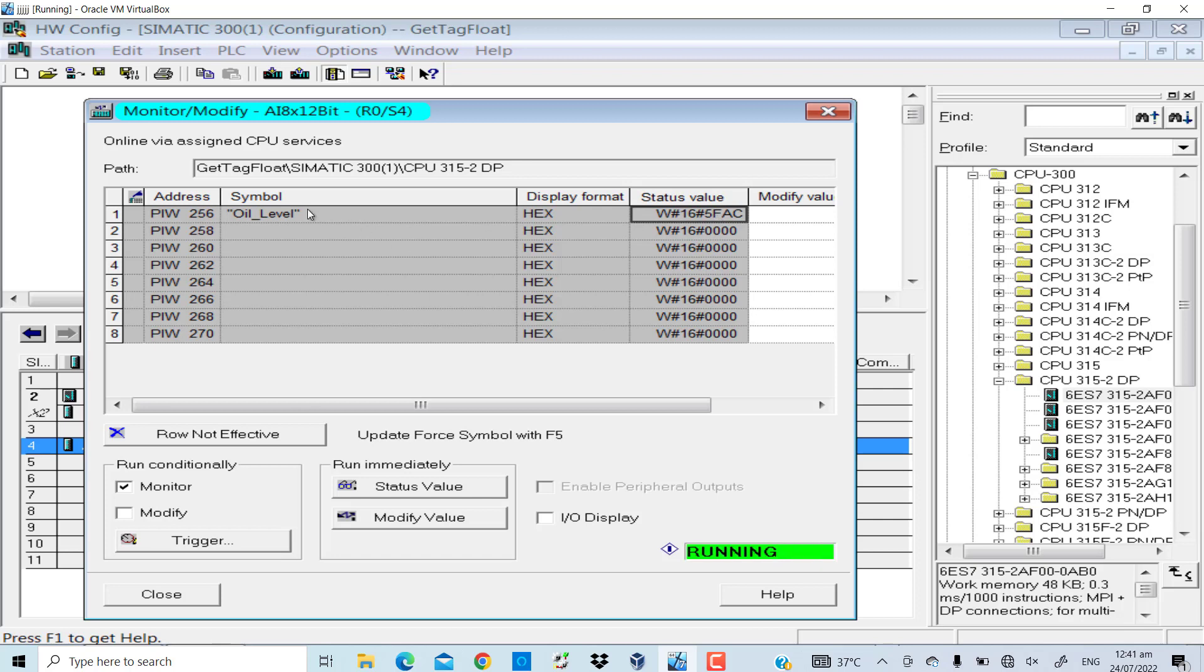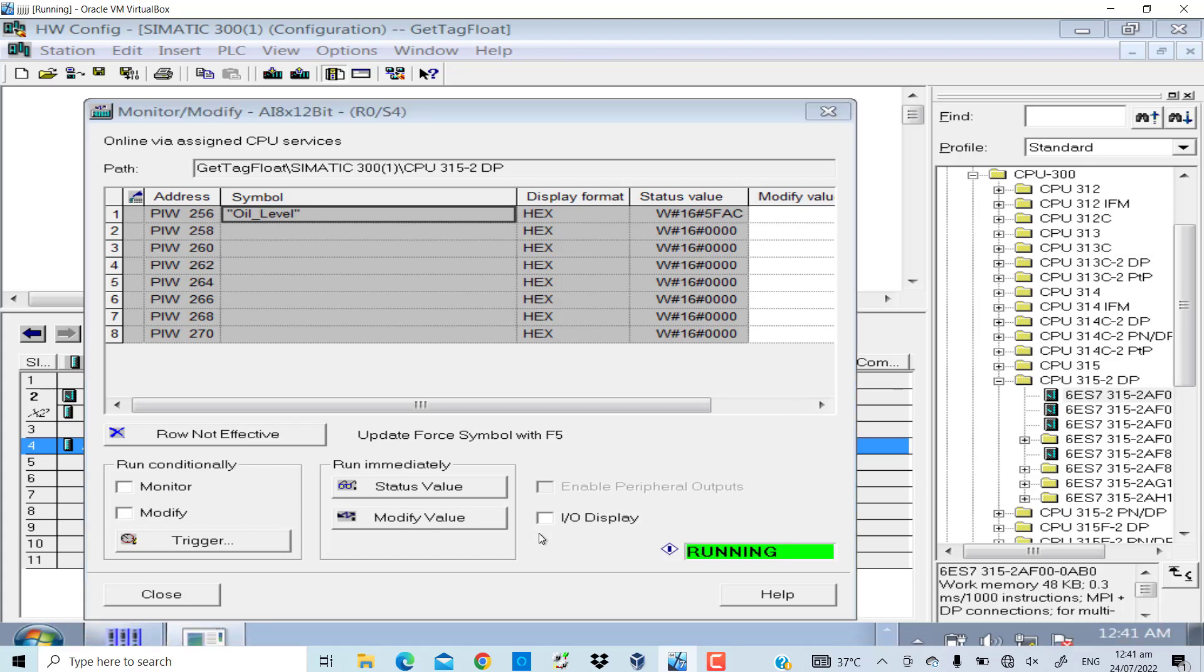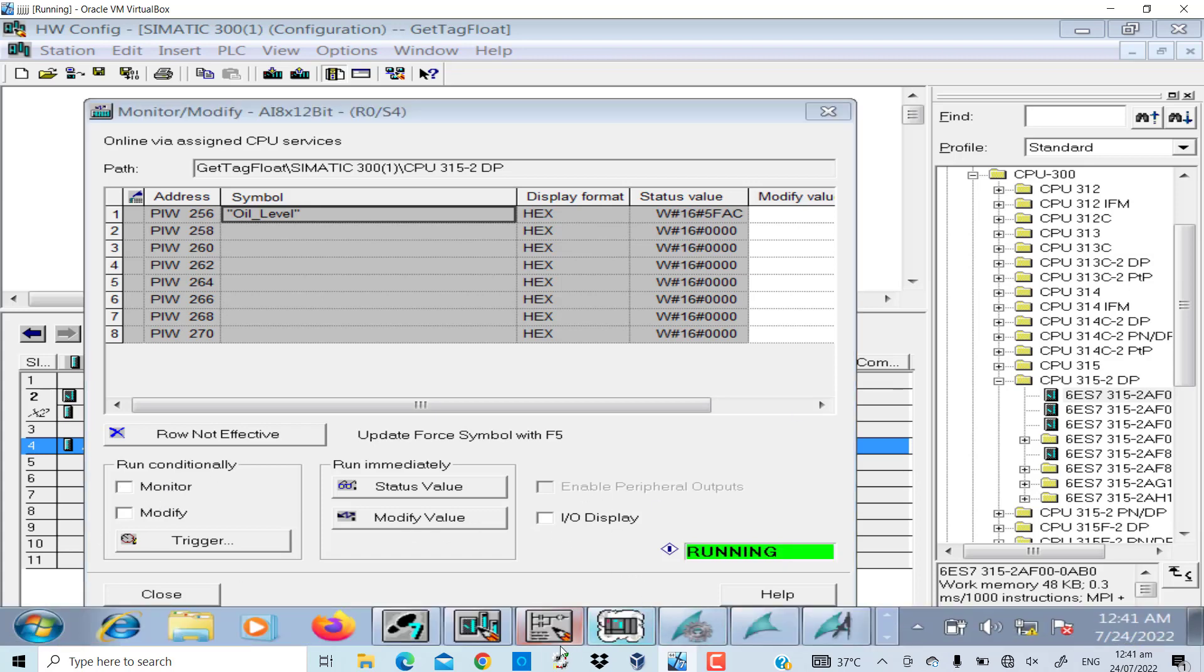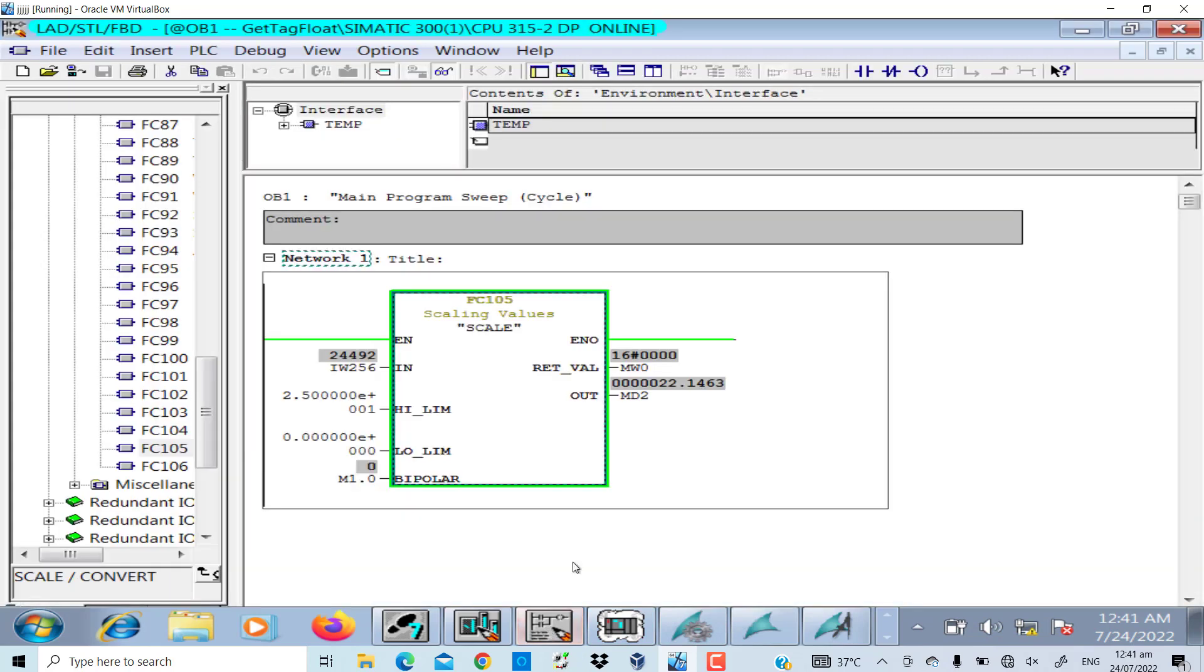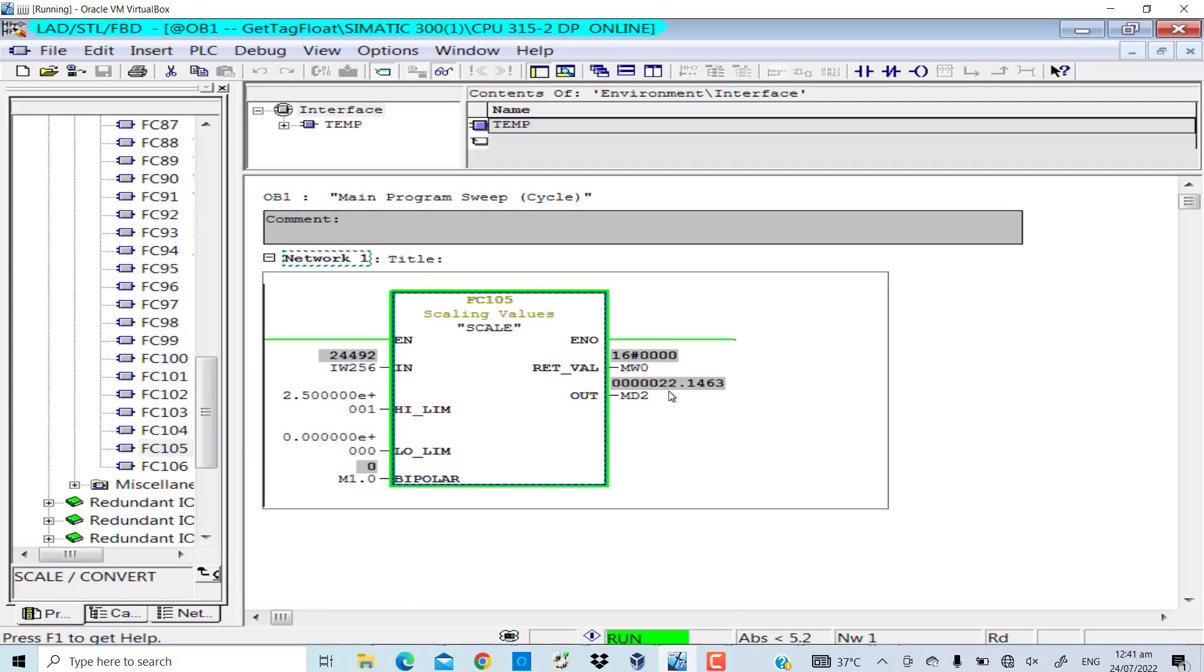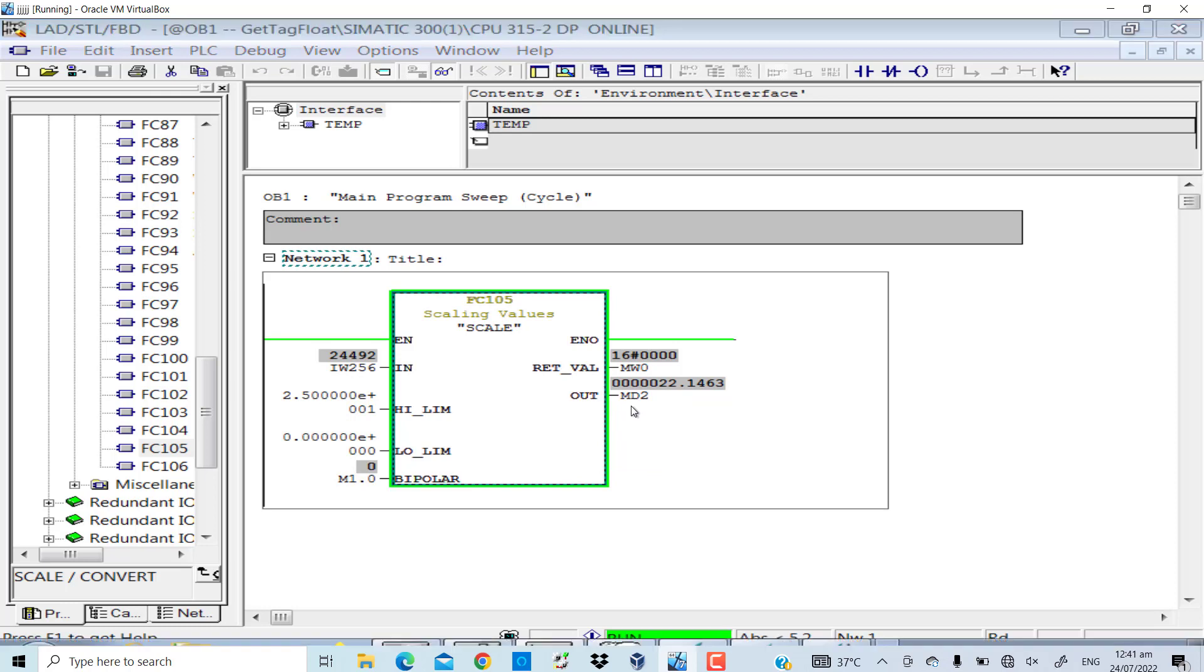The oil level is scaled according to the logic. The value 22.14 is the actual value of the oil tank level on the scale of 0 to 25. I want to show it in percentage, so in the first place you need to add MD2 to the tag management section of WinCC.